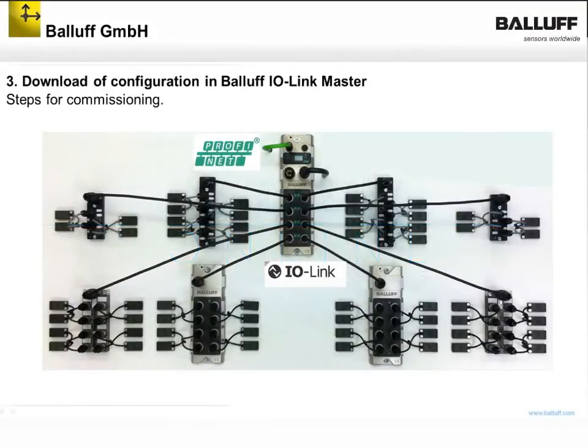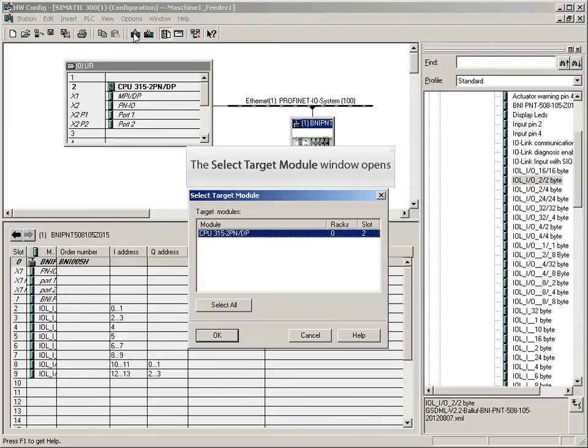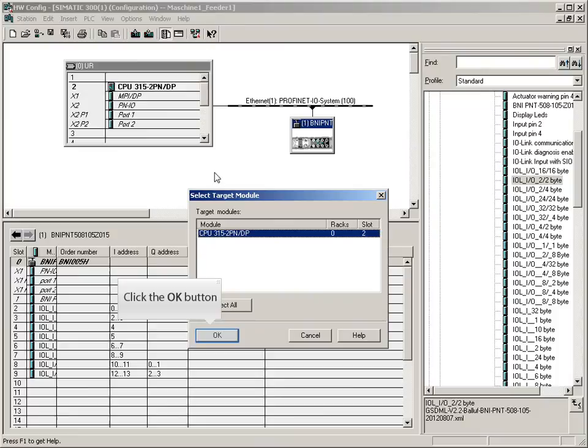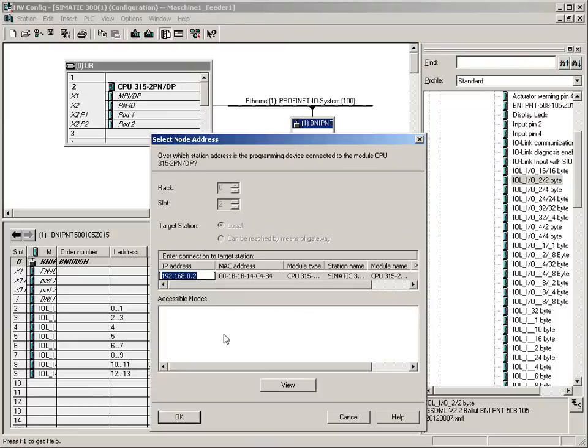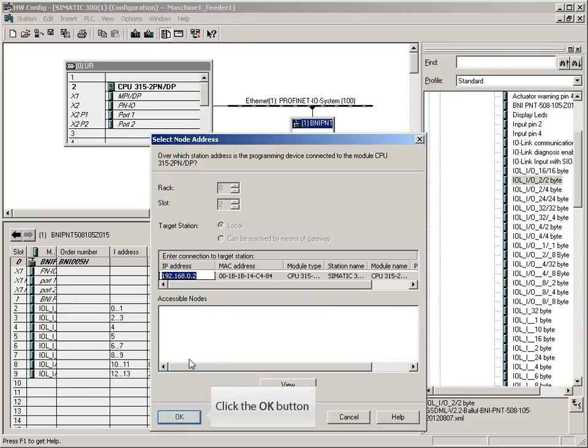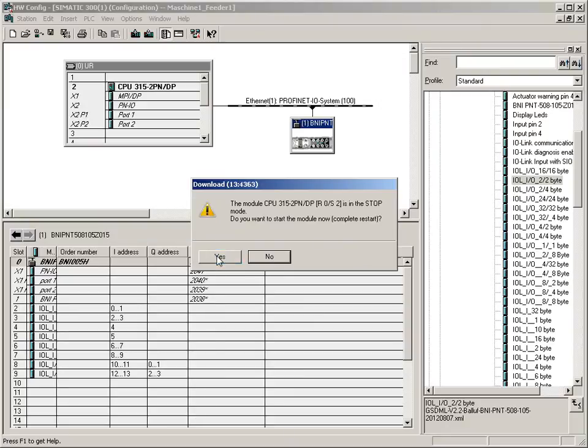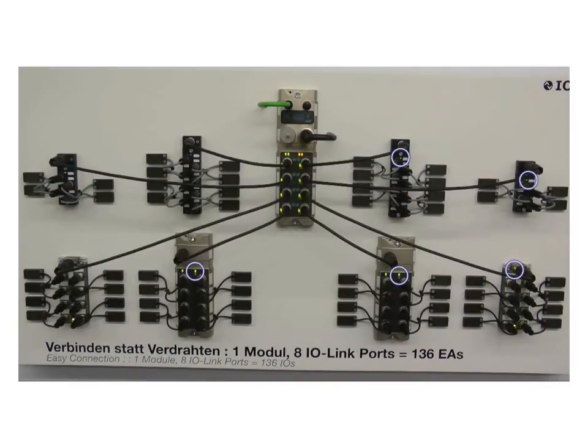The download procedure: Next step is the download in the hardware. Click on the icon download to module. Here the CPU connected with the programming device is now displayed. The connection is established between PC and the CPU. Confirm or change the IP address so the download takes place. OK, download completed. The device is currently in stop condition and will be started. The network communicates now. The IO link communication is indicated by the negative flash of the IO link LED.